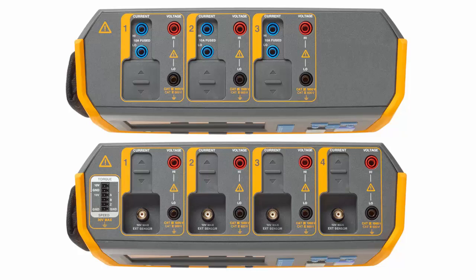Each model has the capability to add a motor option which is shown here. This has six inputs which are basically inputs for speed and torque. With that information you can measure mechanical energy or mechanical power and compare that directly with the electrical power to measure efficiency on motors.